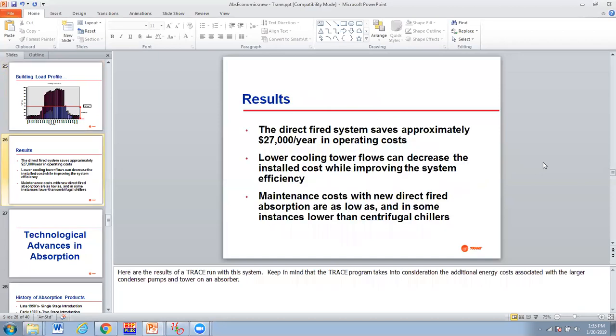Okay, so the results show that the direct fired absorption system saves approximately $27,000 a year in operating cost. Lower cooling tower flows can decrease the installed cost while improving system efficiency. We'll see that some of the more recent chillers, especially Trane, who is talking about theirs, can reduce condenser water flow from the typical 4.5 GPM per ton for this type of absorber down to about 3.6 GPM per ton, which then means you don't have to buy as big of pumps and maybe pipe size down a little bit and this, that, and the other. Maintenance costs with new direct fired absorption are as low as, in some cases lower than, centrifugals. It surprises me a little, but I trust that's good information. And again, they've used the TRACE program to quantify the numbers in this study.